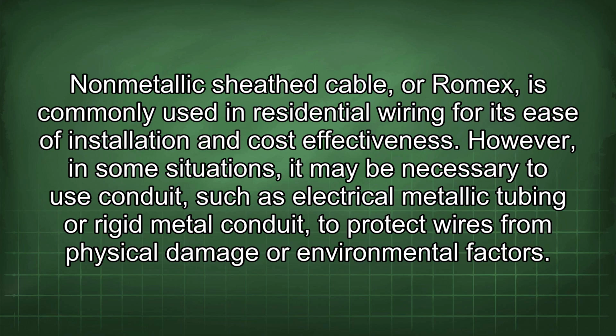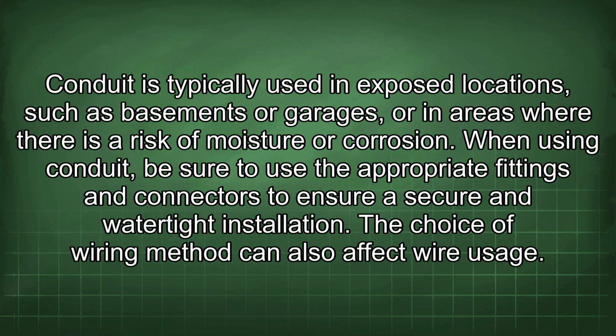Non-metallic sheath cable, or Romex, is commonly used in residential wiring for its ease of installation and cost-effectiveness. However, in some situations, it may be necessary to use conduit, such as electrical metallic tubing or rigid metal conduit, to protect wires from physical damage or environmental factors. Conduit is typically used in exposed locations, such as basements or garages, or in areas where there is a risk of moisture or corrosion. When using conduit, be sure to use the appropriate fittings and connectors to ensure a secure and watertight installation.